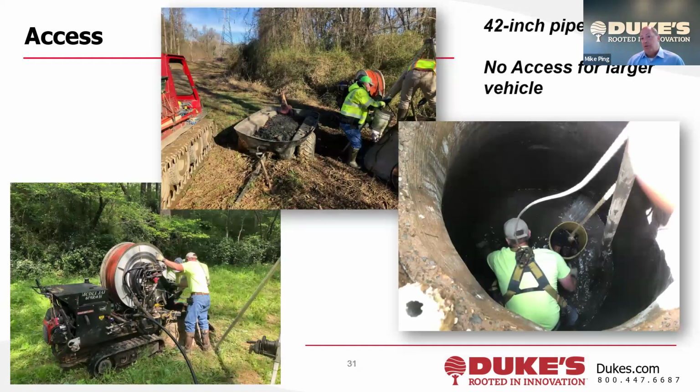So here are some interesting pictures. I'll begin in the bottom left. That's a little better picture of an easement machine. You can see the black hose from the truck parked some distance away, probably within 1,000 feet. This is a hose extender that's getting extended out. It's doing the jetting, and it has the hydraulic system to pull or rake the debris back to the manhole. That's a mechanical feature. It goes out on its own because of the jetting action, and then it gets pulled back mechanically to bring the debris back.